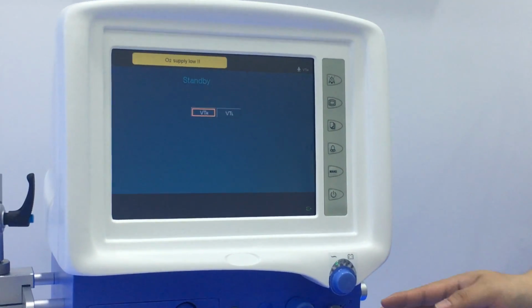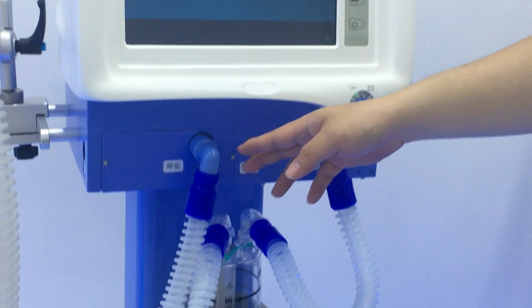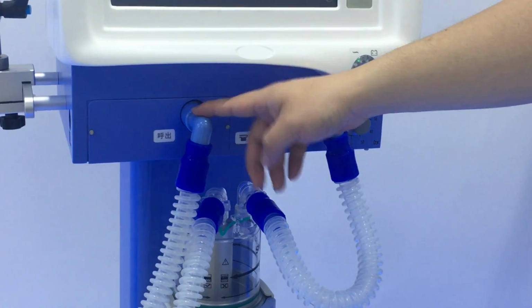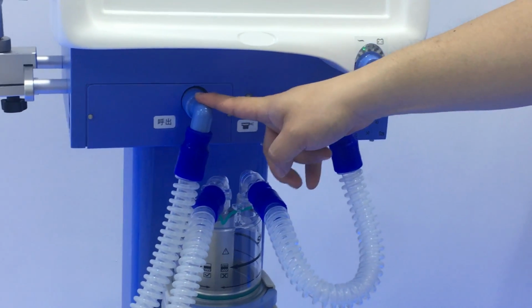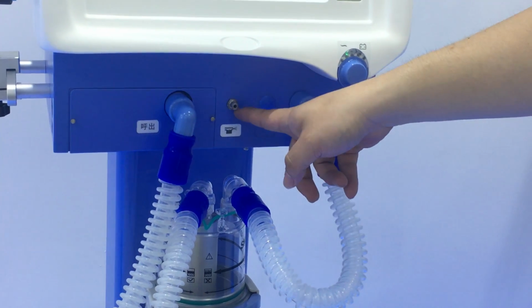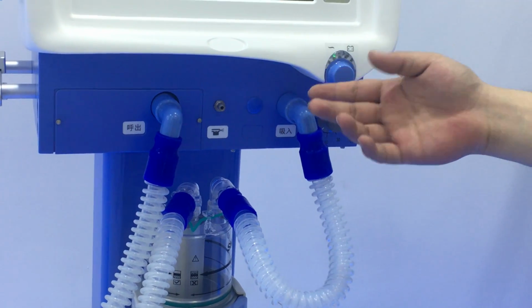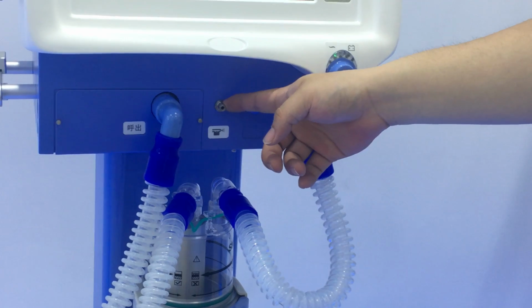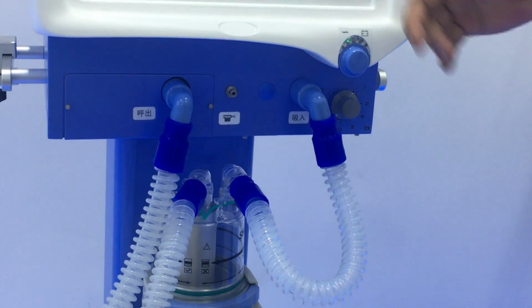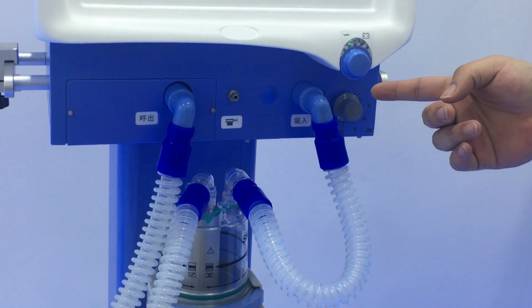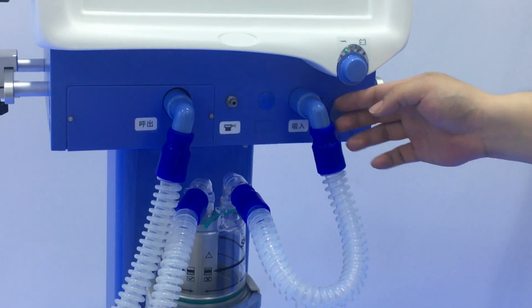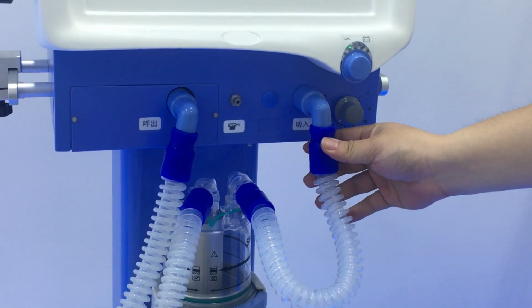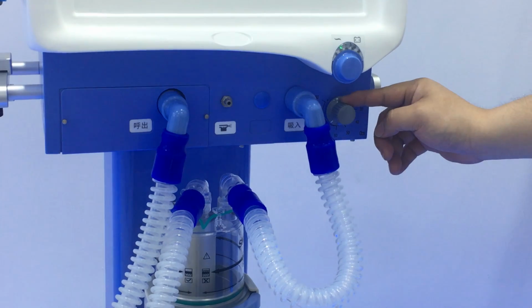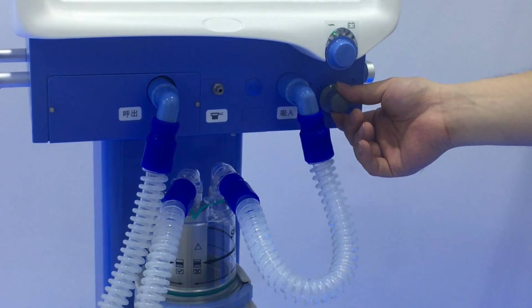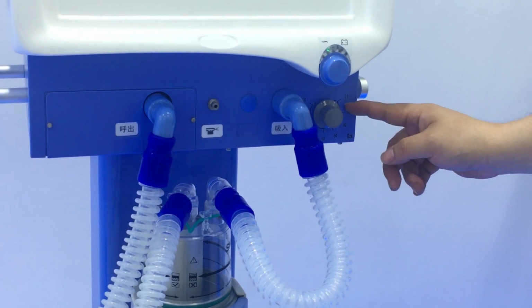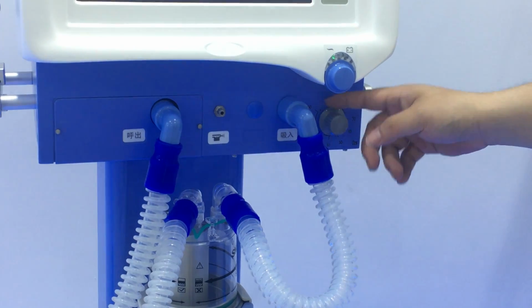Okay, then let's turn to this part. Here you can see there are 2 ports. The first port is for the expiration port, and here on the middle side there is the port for the nebulizer tube. We connect the nebulizer tube, and then we press the button. It will automatically use the nebulization and atomization function. And here this port is for the inspiration port. And also for the oxygen adjusting, we are using the rotate button here from 21% to 100%.